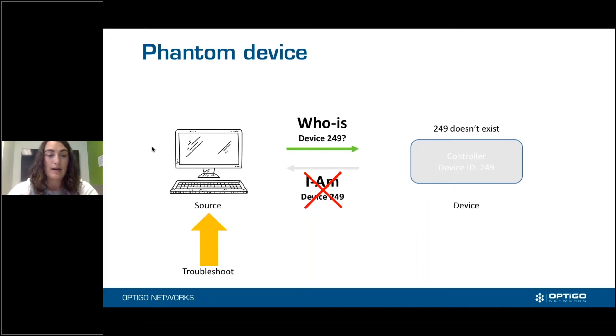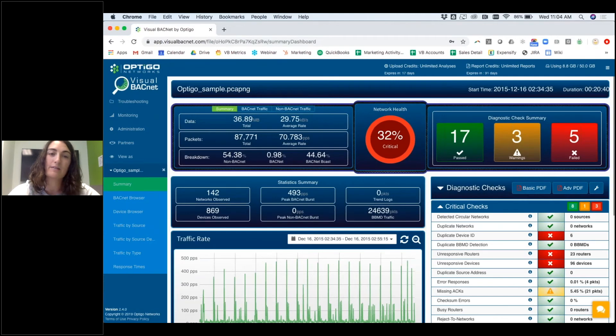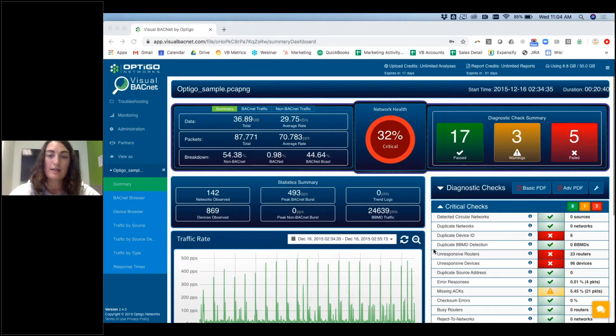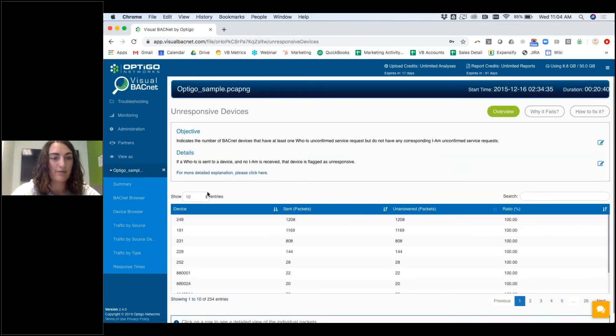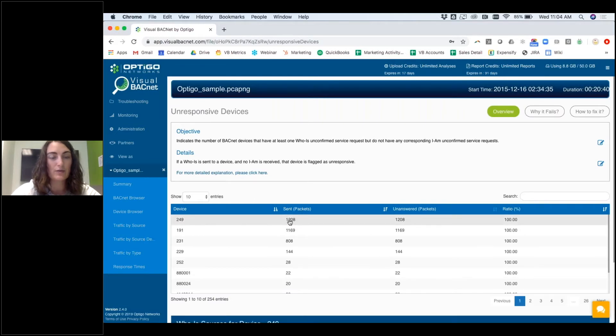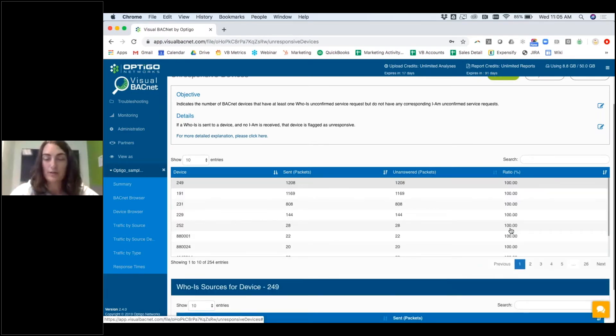This is a phantom device scenario. Let me jump into Visual BACnet. This is a file in Visual BACnet — you can get here through Troubleshooting or Site Monitoring. We're going to go into the Unresponsive Devices diagnostic check. At the top of my file is device 249. In this case, device 249 had 1,208 packets sent to it and 1,208 packets were unanswered — so 100% unresponsive. At the very end of this list, we do include some partially responsive devices, but we don't count those in your unresponsive device total.